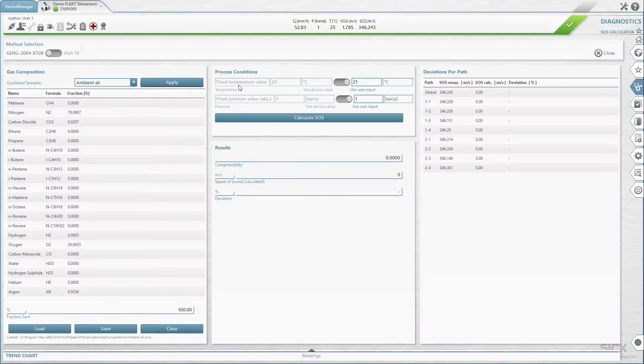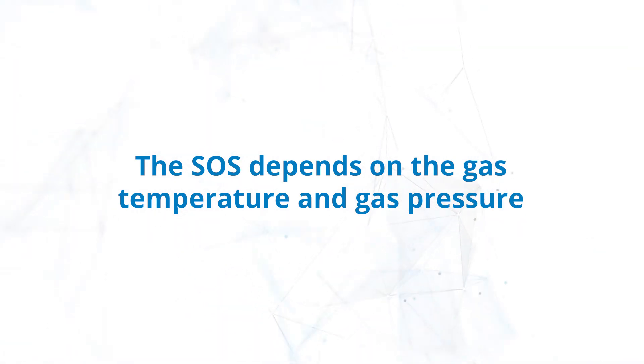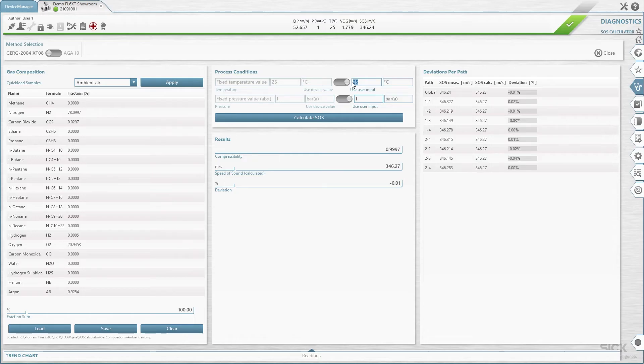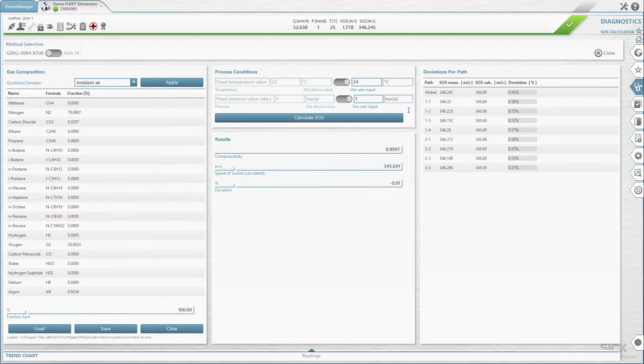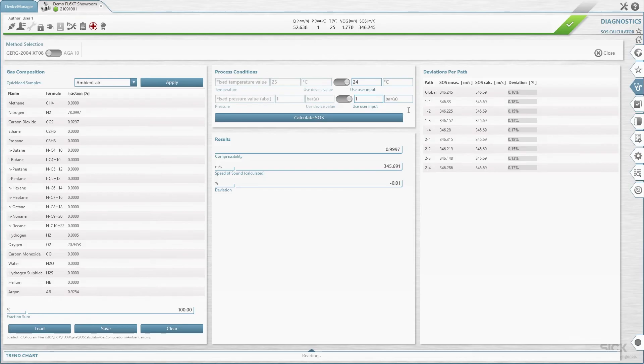After you have defined the composition of the application gas, you can calculate the speed of sound. The speed of sound also depends on the gas temperature and gas pressure. In the panel Process Conditions, define the temperature using the temperature control and the pressure using the pressure control. Start the speed of sound calculation by clicking on Calculate SOS. The theoretical speed of sound will be displayed in the results panel alongside the compressibility and speed of sound deviation values measured by the device.